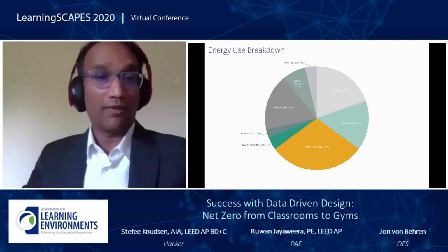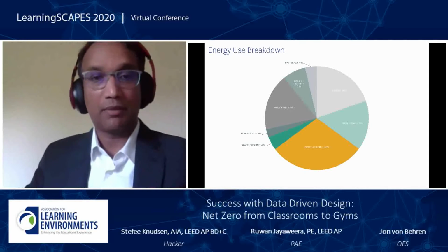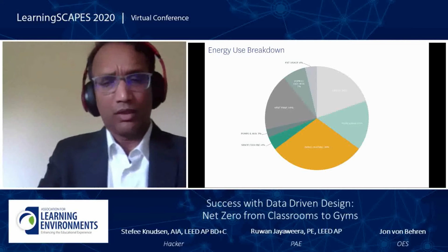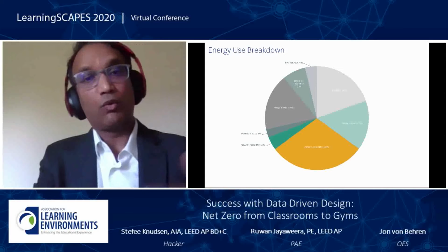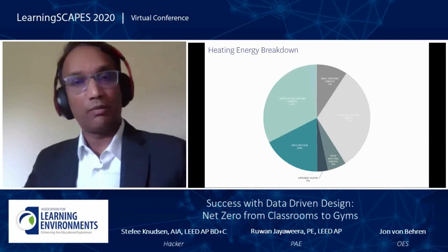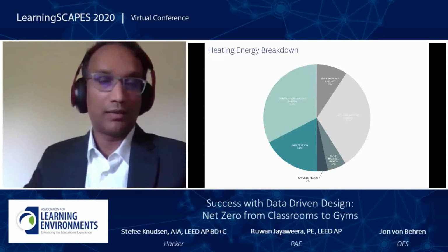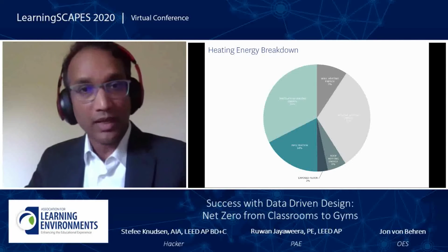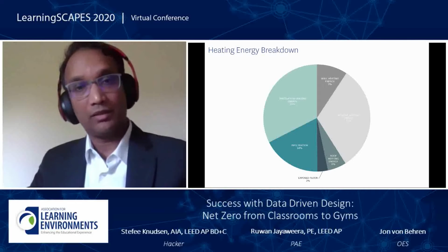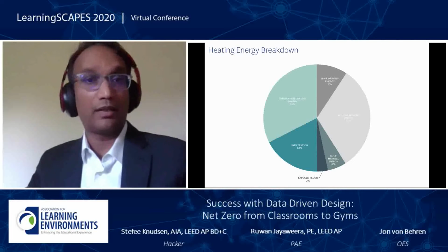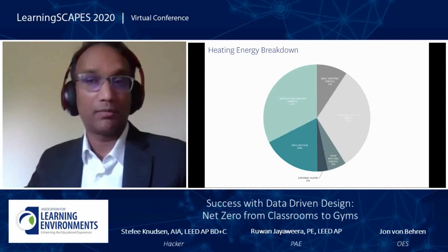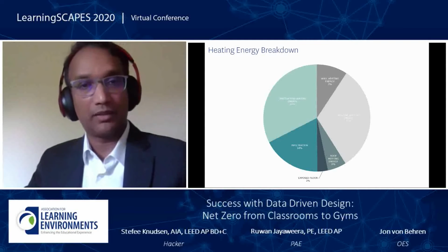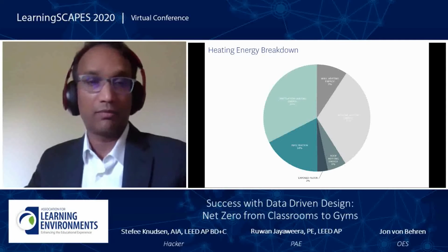Now we can dive a little deeper. Looking at the heating piece of the pie, since it's the biggest piece, we ask where does that loss occur? We have that data. It shows that in this type of building, a lot of it has to do with windows, so a lot of heat is lost out the windows. Also, a lot of the energy used to condition the required code-minimum ventilation takes up energy as well. So those are two big items we can work on.